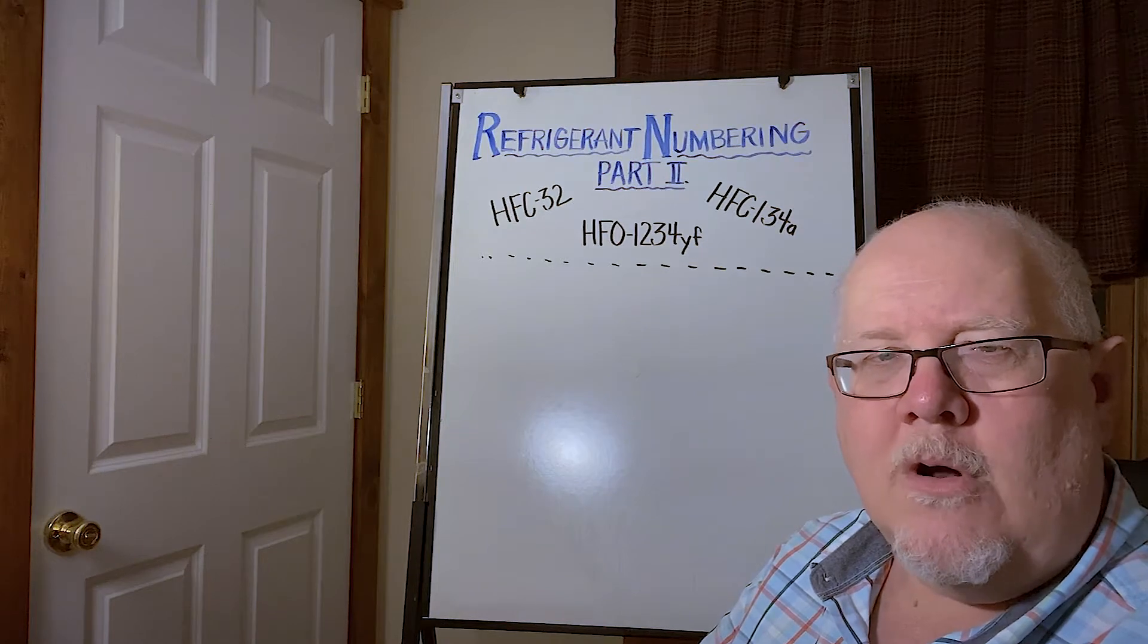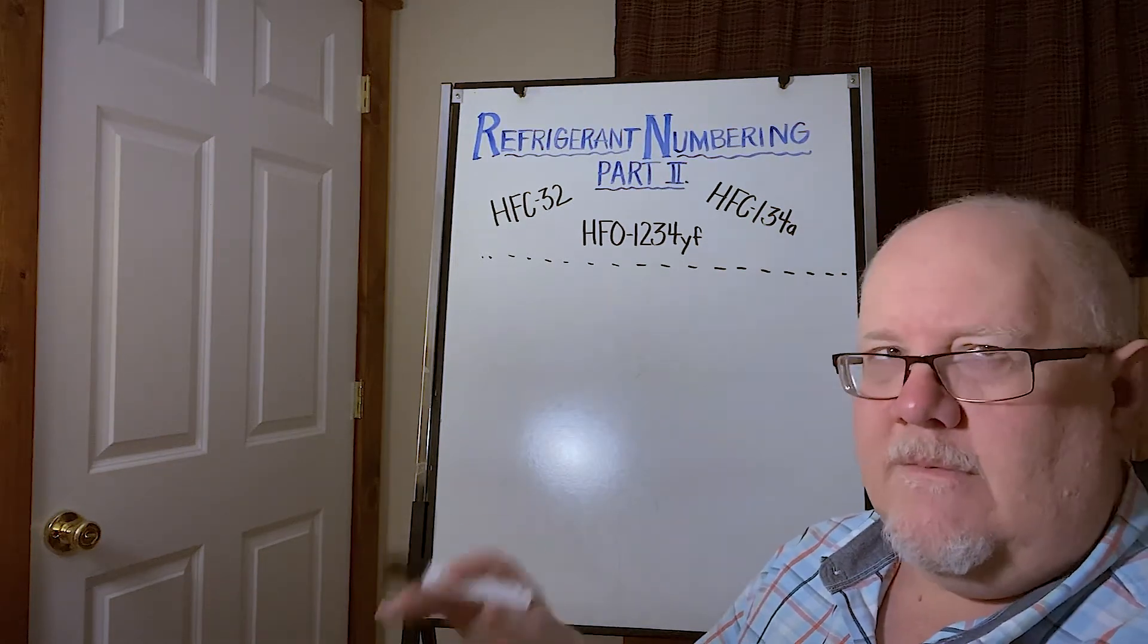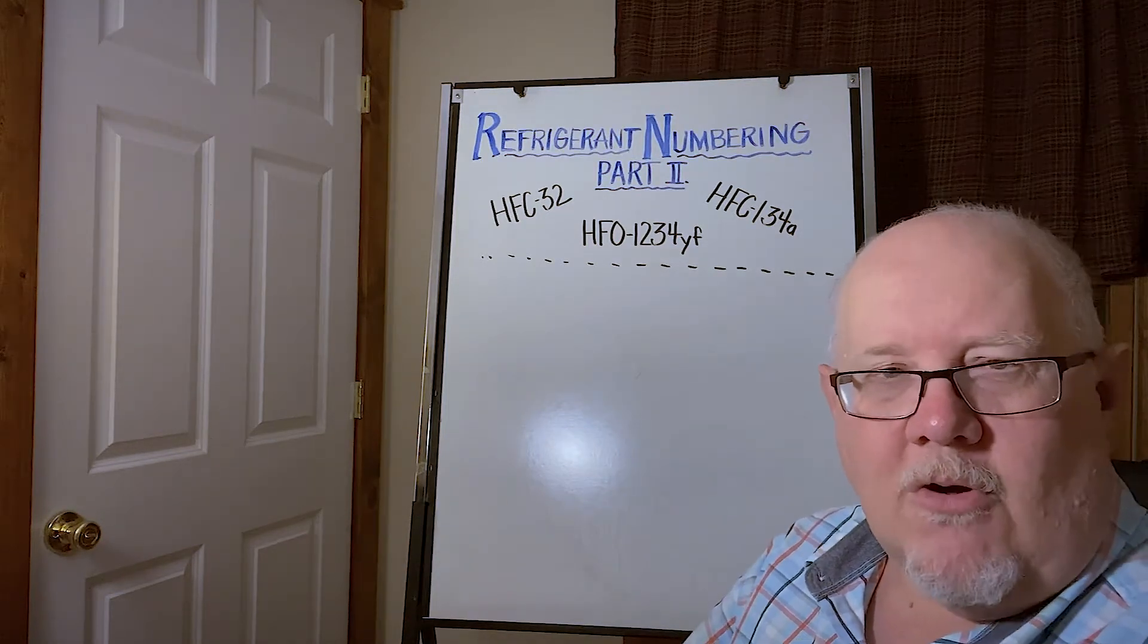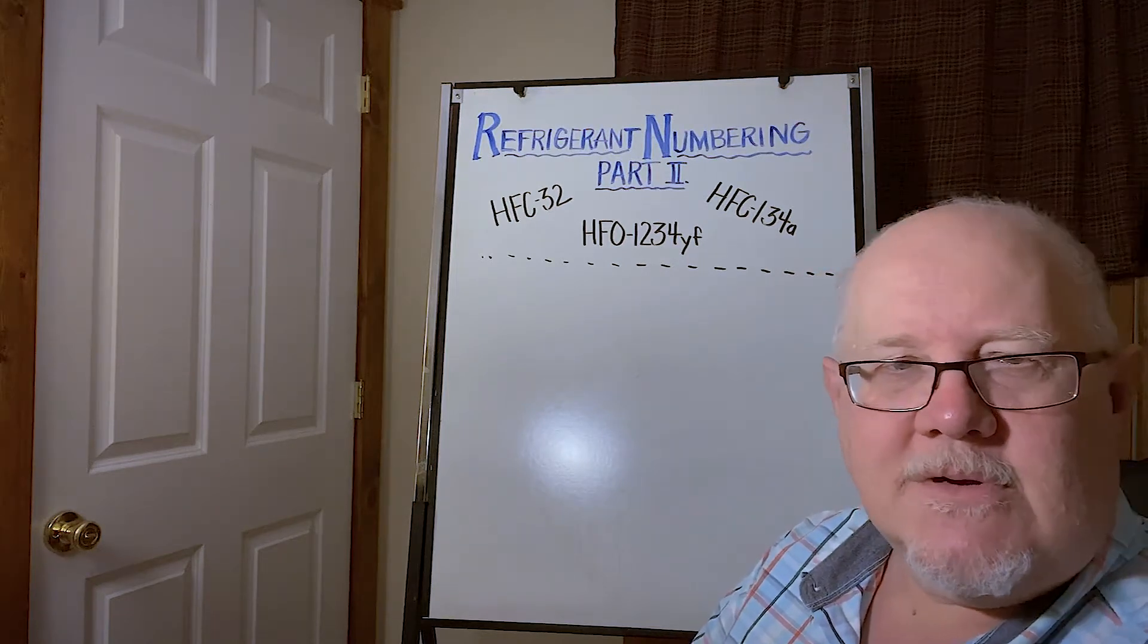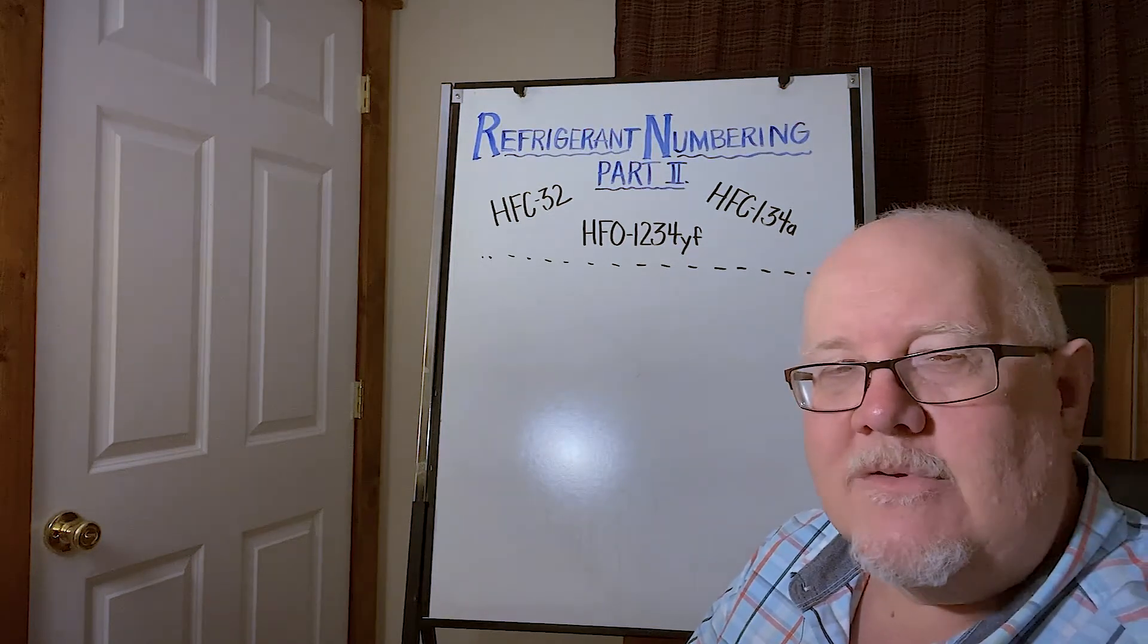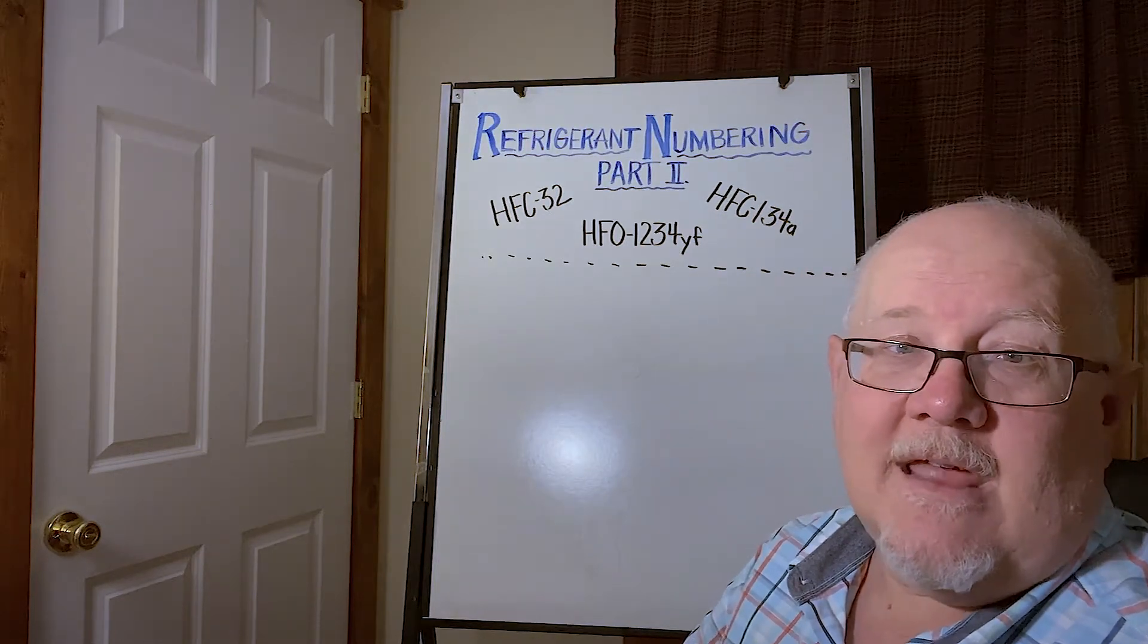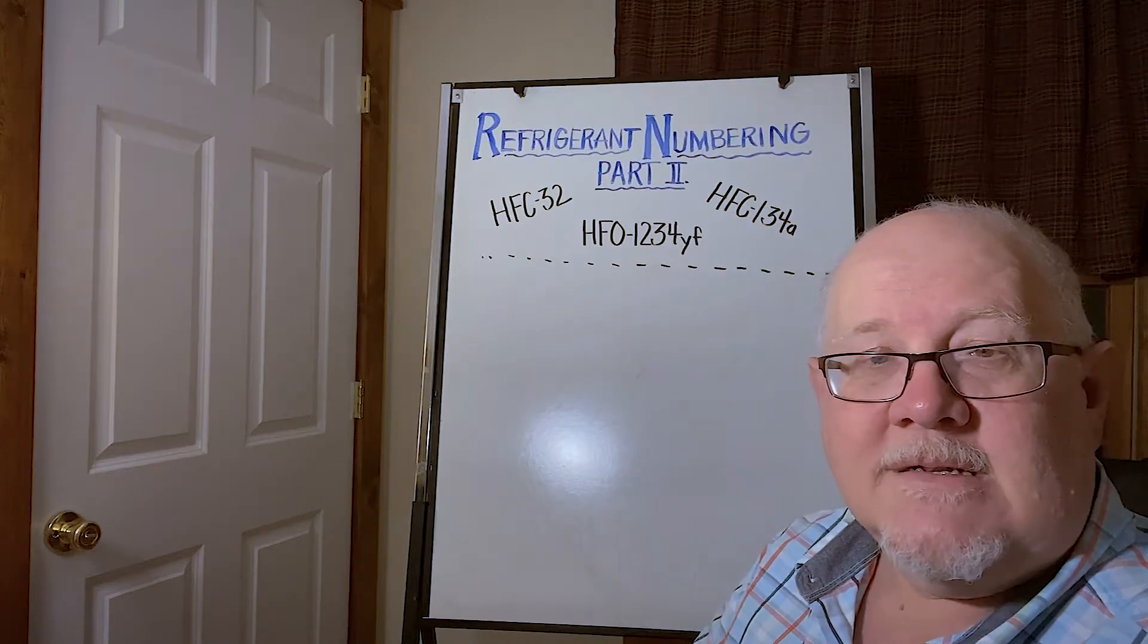So there are 401, 412, 420, and they just are assigned sequentially. It's been going on for a while. I think we're up in the 480s now with some of the newest refrigerants, but we still have 401, 402 still around and being used. A lot of numbers get assigned that end up never being commercial products, but they get assigned during the development and R&D phase.